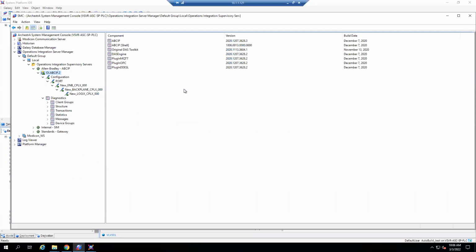Gotcha. I don't have experience with FactoryTalk Gateway, but in my experience, the software component that is provided by Allen-Bradley is not streamlined for System Platform. RSLinx and FactoryTalk Gateway are built by Allen-Bradley to be compatible with different OPC servers and different end software to communicate with. So it's open-ended, and as a result, there's more configuration that needs to happen. But the ABC IP driver in System Platform is specifically built and streamlined for the Allen-Bradley PLCs. In my opinion, it's better to go that route because the process is streamlined. It's set up specifically for this. Meanwhile, if you had to go through RSLinx, there would be more configuration, because there are just more parameters that need to be configured.